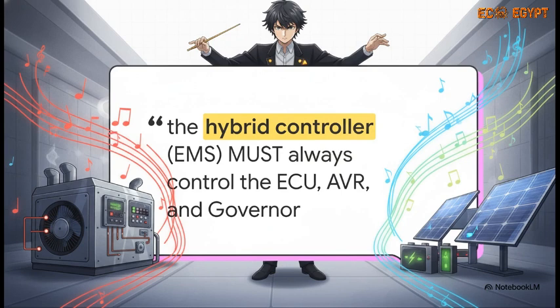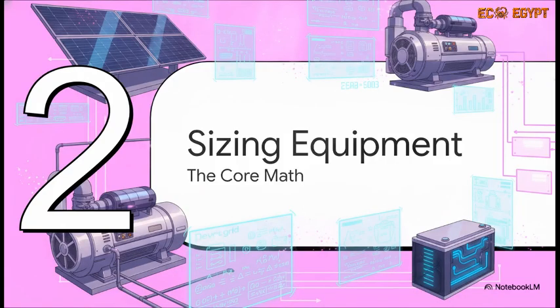Think of this control architecture kind of like a symphony orchestra. The hybrid controller, that's your conductor. The diesel generator sets the rhythm, and the PV and batteries fill in the melodies. But the golden rule here is centralization. You can literally never delegate the control of the generator's safety-critical functions, like engine speed or voltage stability, to an inverter. The hybrid controller has to maintain total, centralized authority to keep the island stable. Moving right along to Section 2, sizing the power equipment.